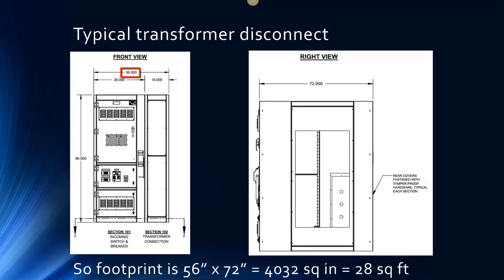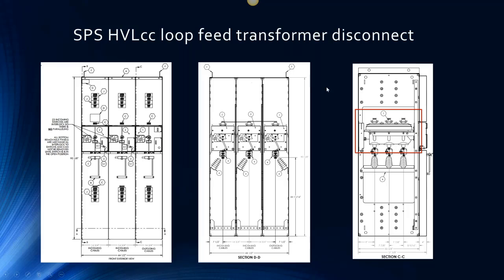And let's take a look at what our typical transformer disconnect would look like if it's air insulated. That unit is going to be 36 to 38 inches wide, and is also going to need a cable transition section to connect to the transformer, to translate the bus so that it can connect to the transformer, whether it's liquid or dry. And so that ends up being around 56 inches in linear width. And it's metal enclosed gear, so it's going to be around 72 deep. There are cases where we can get it less than that.